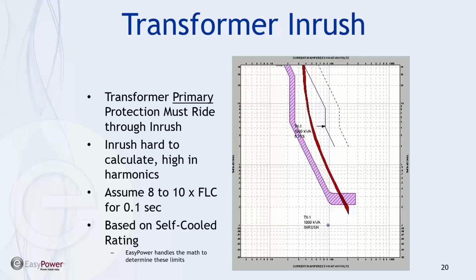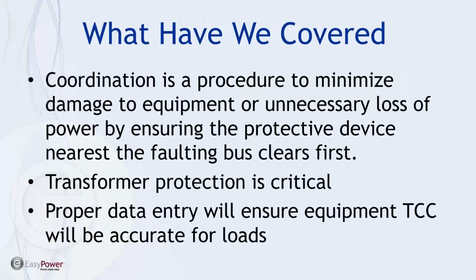All right, so what we've primarily done is emphasize the TCC plots in EasyPower. We want to make sure that we understand the procedure to minimize the damage to the equipment and defining our coordination policy, recognizing that in fact there may be some impact on incident energy calculation, and we'll be able to explore that when we get into the tool use. It's important to make sure we have the proper protection on the transformer, and then our data entry is of primary importance because the TCC plot is based upon the data that we've utilized.